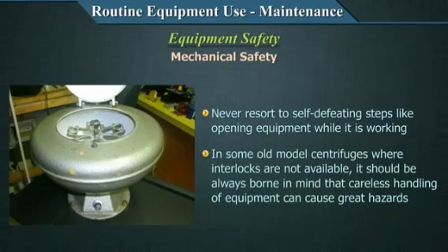In some old model centrifuges where interlocks are not available, it should always be borne in mind that careless handling of equipment can cause great hazards. Sometimes it's seen as a practice that even before the centrifuge stops, the lid is opened. It's a very risky practice because of two things. One is aerosolization, because it's a biohazard. Most of your samples will have some pathogens that can be airborne. That's a very hazardous thing to do. And also sometimes the test tubes break and fragments of glass can fly out and injure you. So there are so many hazards because of opening a centrifuge while it is working.